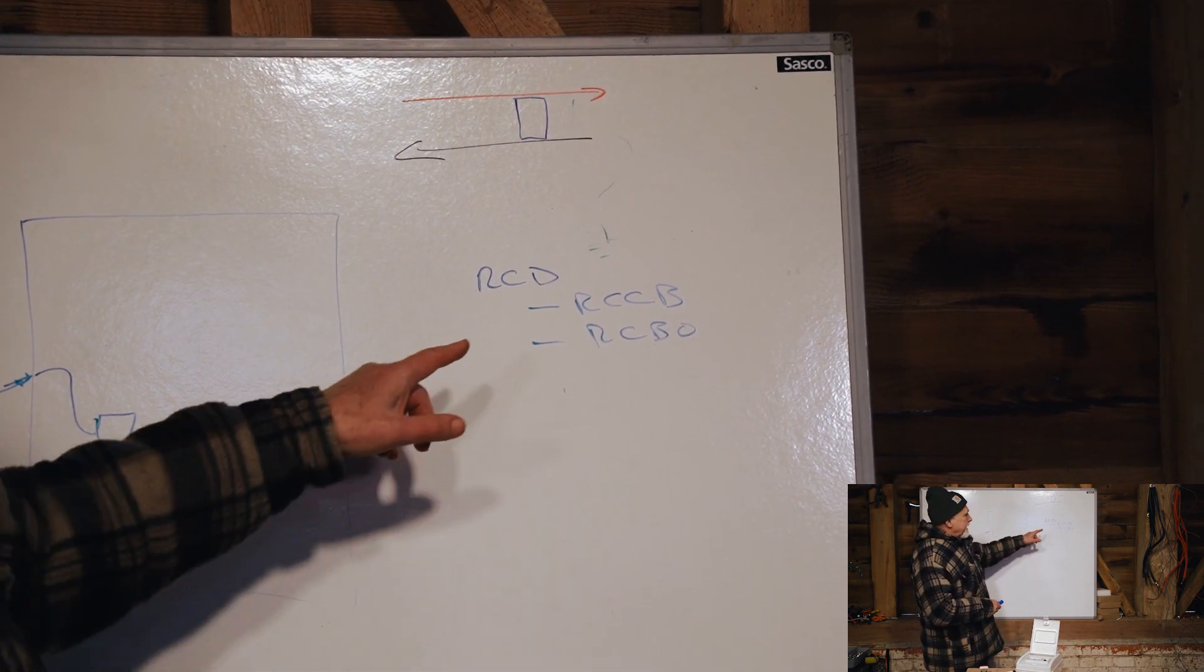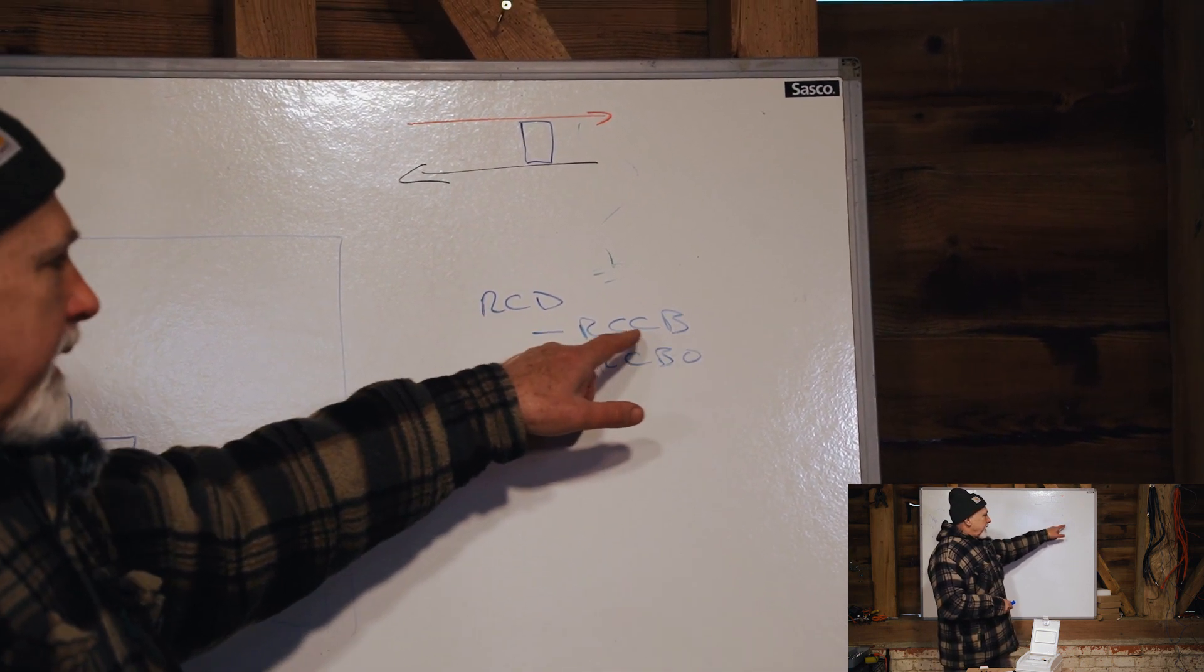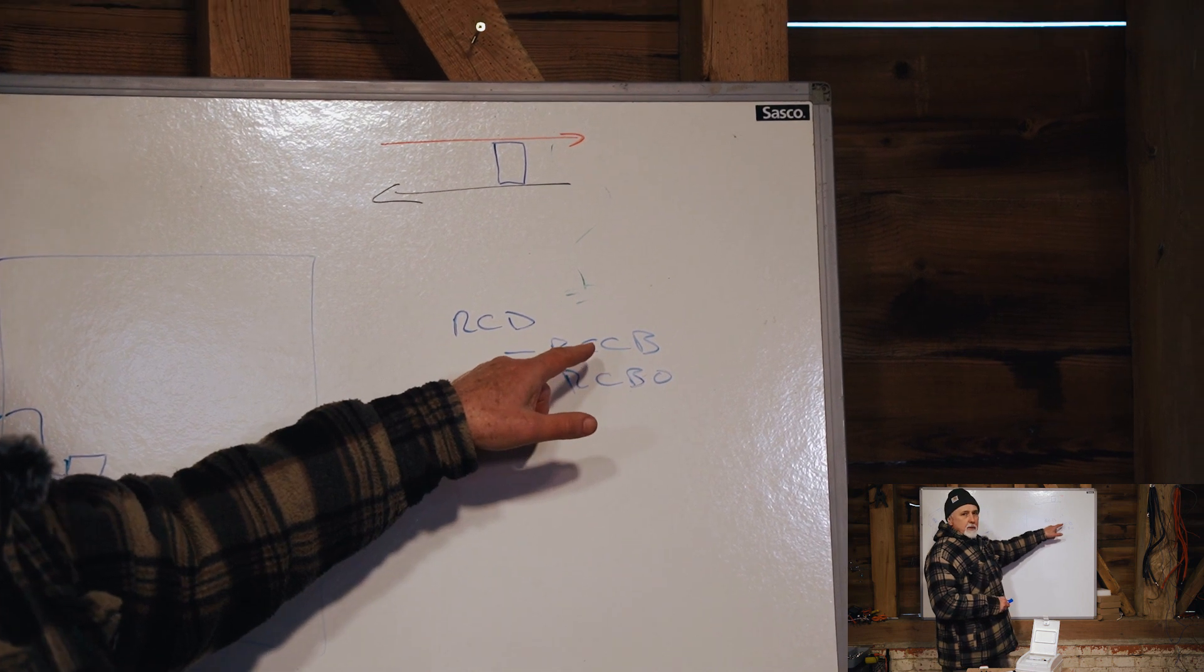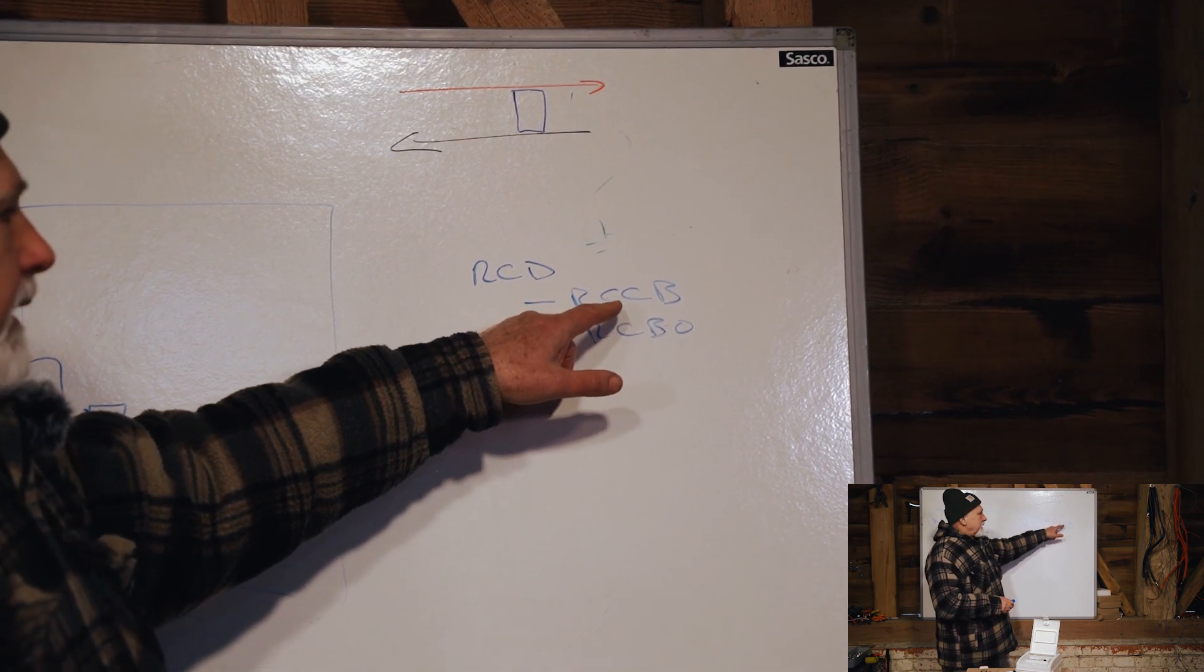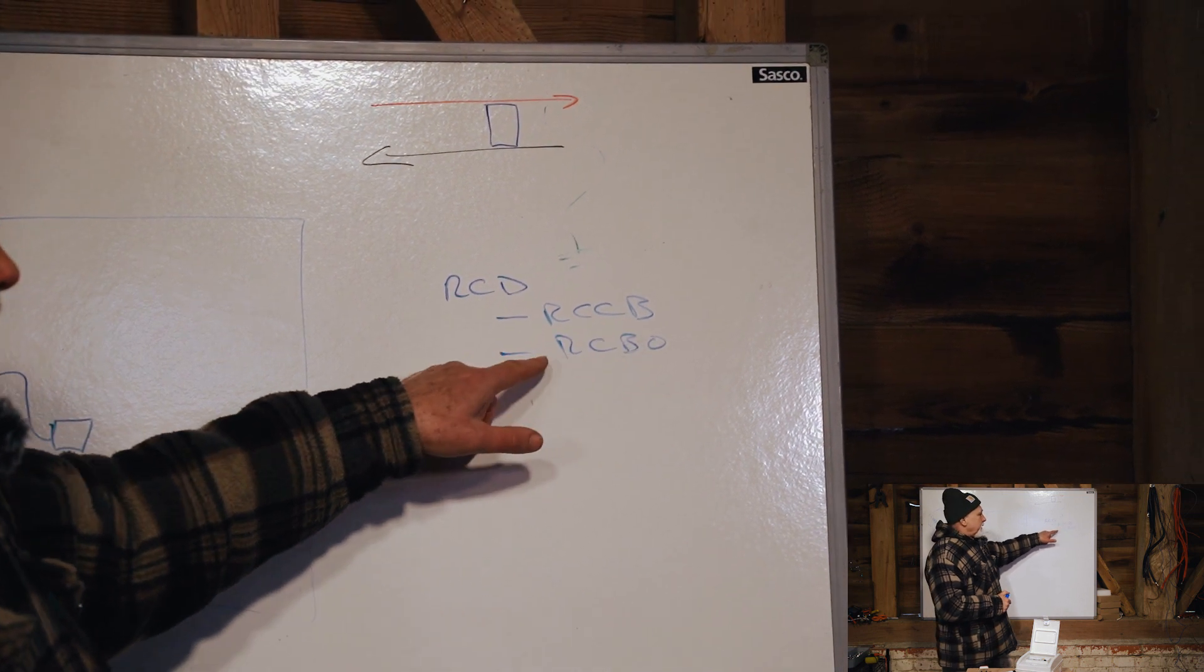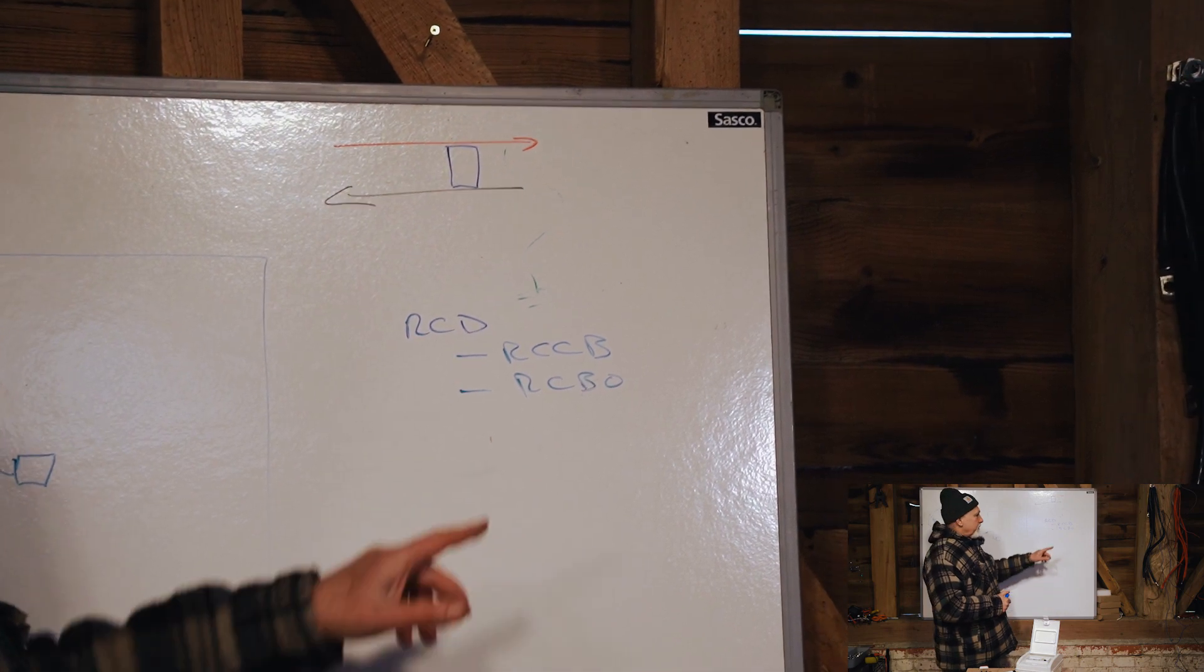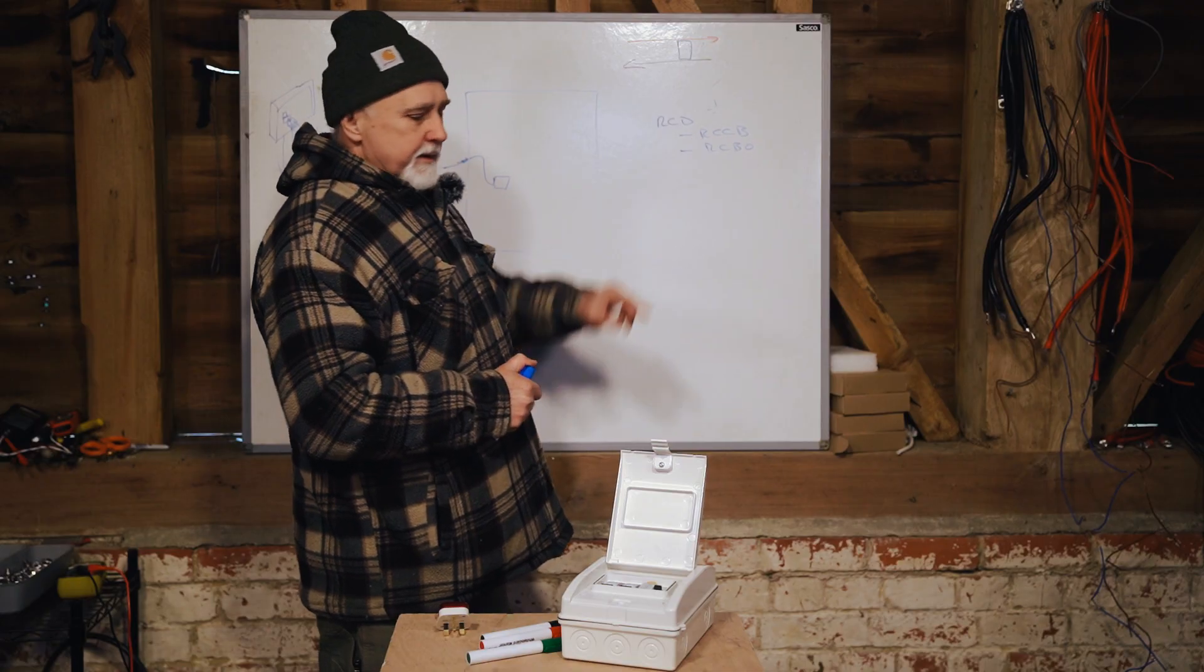So basically, if you're using an RCD or an RCCB, which are sort of the same thing in most people's minds, you also need to have a circuit breaker as well. If you're using an RCBO, you don't need an additional circuit breaker because this does it all for you. So this does a lot more than this.